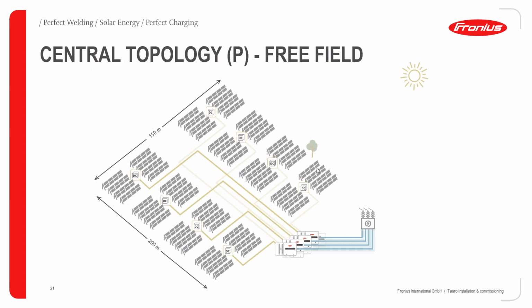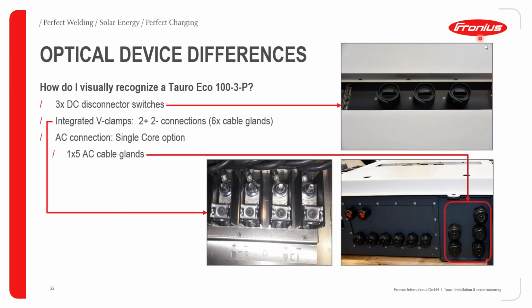Similarly, looking at a free field installation with a centralized topology, a similar approach applies: all the strings are collected, and then from the string DC combiner box, you come into the inverter. So how do you recognize a pre-combined version of the Tauro inverter? This is, for instance, a 100 kilowatt inverter pre-combined.